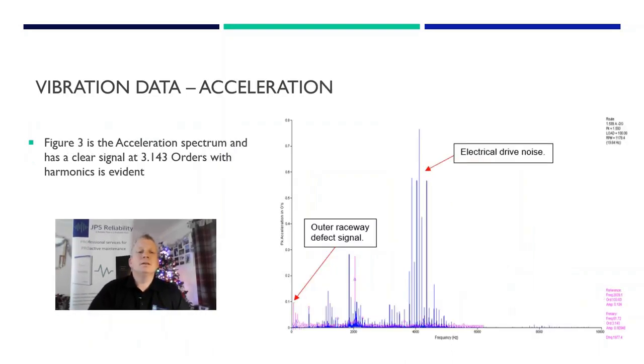Now, the acceleration was a giveaway. You can see here we got a low level outer race signal coming up and a big mound of noise, which is sidebanded by the 2x pulse frequency from the drive. So that's whatever hertz the drive is putting out times 2 because of north and south. And that is a dead giveaway for electrical issues. Now, electrical issues is a really big, huge thing. Everyone's going to variable speed drives, and we're finding a lot of installation anomalies. So this could be down to incorrect earthing, no earthing, poor earthing, lack of greasing, lack of maintenance of the drive. Now the drive itself alone is not an issue. It's how the drive is fitted to your system and the cables you use and the screening.